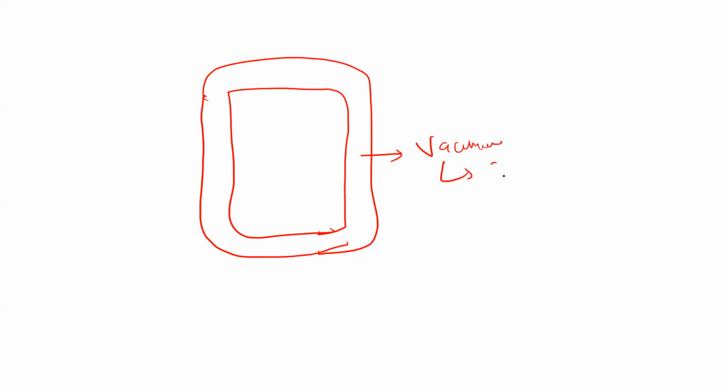And they're coated with a layer of perlite. Perlite is a substance which acts as an insulator so that it doesn't conduct heat, it doesn't get heat from the external atmosphere. So that is why this vacuum layer is coated with a layer of perlite. The purpose of perlite is to increase the insulation.